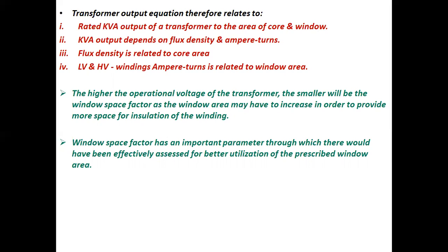Both the points, I again repeat. The higher the operational voltage of the transformer, the smaller will be the window space factor, as the window area may have to increase in order to provide more space for insulation of the windings. Number 2, window space factor is an important parameter through which there can be an effective assessment for better utilization of the prescribed window area.